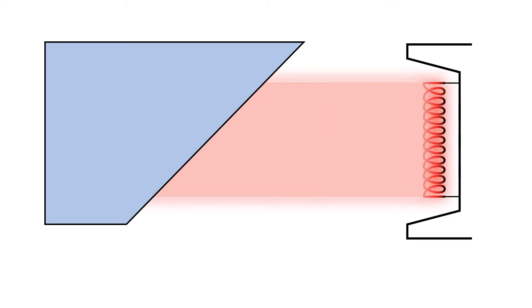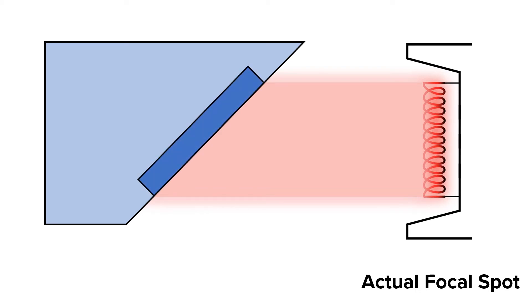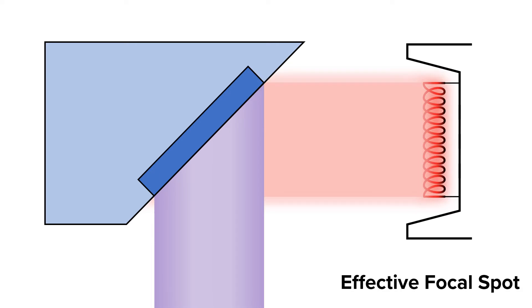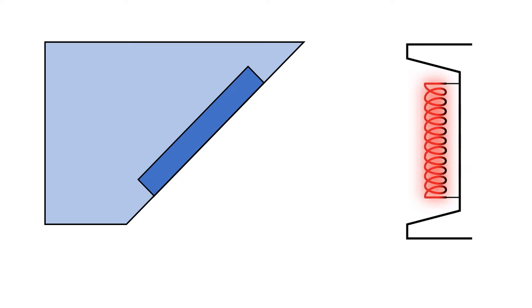Second, the actual focal spot. The actual focal spot is the physical area on the anode that, when bombarded by the incident electron beam, emits x-rays. Third is the effective focal spot. The effective focal spot is the area projected onto the patient. The size of the actual focal spot is determined by the size and shape of the incident electron beam when it strikes the anode surface.